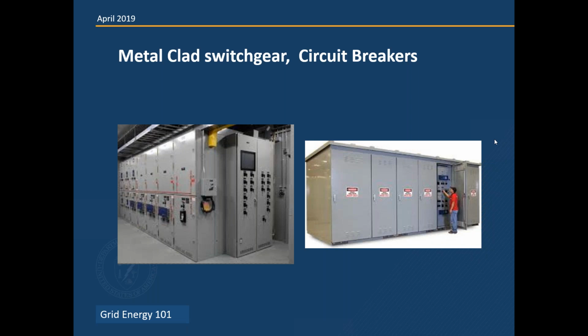And so how we do that, I'll give the example of one of our hydro plants here in Northern California. What they have is two 500 kW diesel generators that are tested weekly. And when they lose potential at the power plant, whether it's a system-wide outage or just a power plant outage, these start on loss of potential. Certain devices open up, the diesel generators automatically start up, they go to 60 cycles and they sit there. And then the generator operator goes over, flips a couple of switches, gets the auxiliary circuits energized on the units, and then he goes through the automatic startup process and starts that generator.